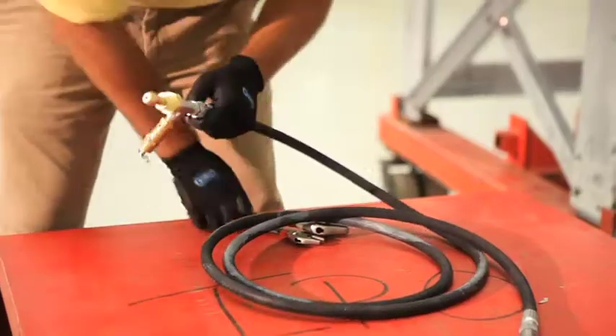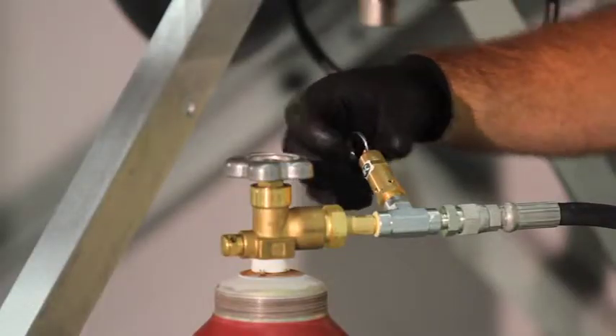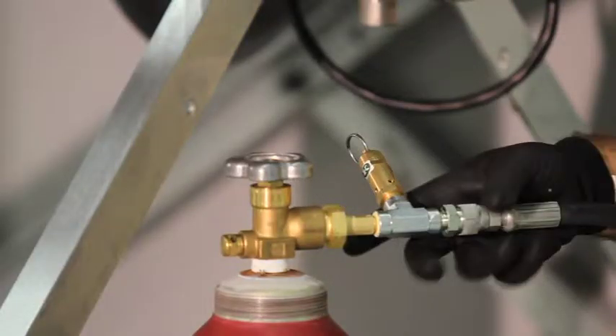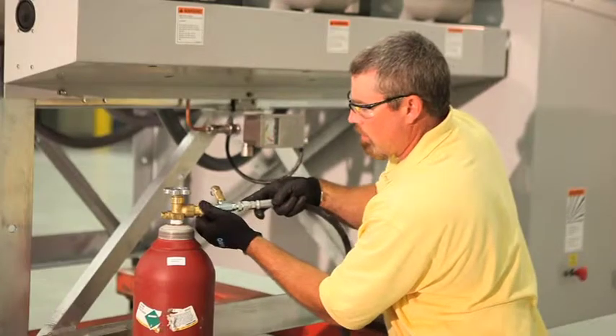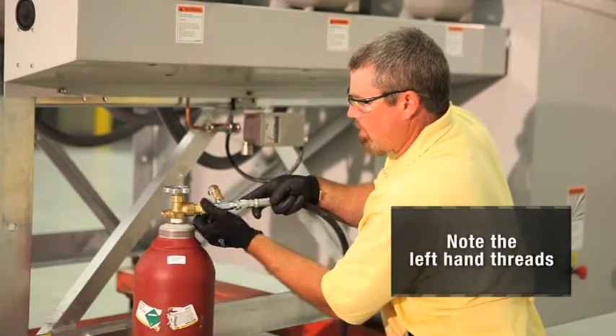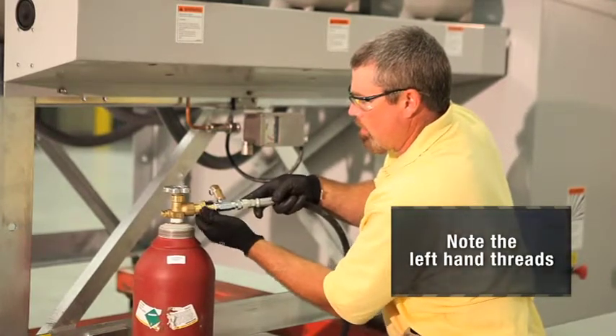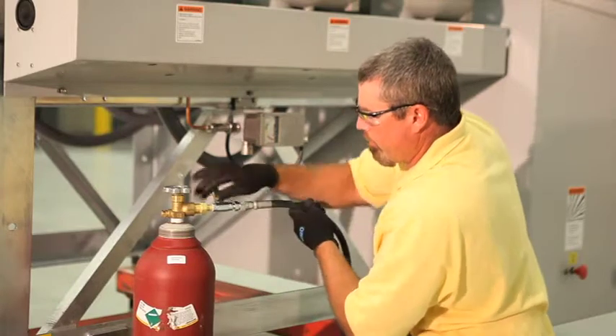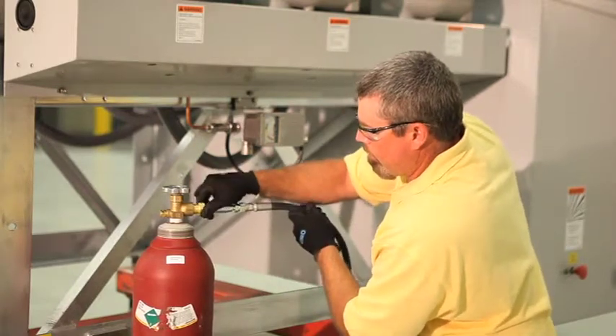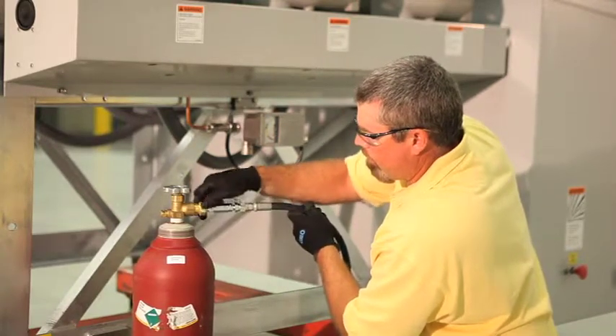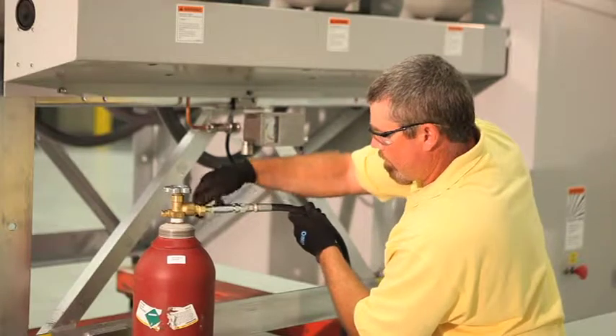The pressure relief valve will prevent overpressurizing the hose or the circuit breaker if the SF6 gas cylinder valve is opened excessively. Take the end of the hose with the relief valve manifold assembly and connect to the SF6 cylinder. The procedure for connecting the hose is critical to assure that SF6 is not lost from the breaker or that air is admitted into the breaker.